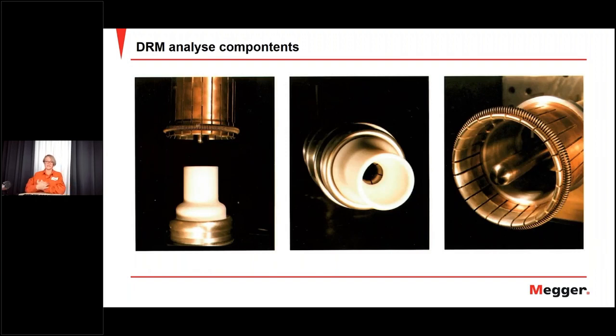So here is a detail of the inside of what you want to evaluate. We have a moving contact here, down here. Here you see it from other angles, so you can see the arcing part and the main part. And here is the main part, and the arcing part is sticking out here. So you want to make sure this is sticking out enough, so it will really take the arcing. You see the upper part here from another angle, and you can see that it has springs and different fingers.